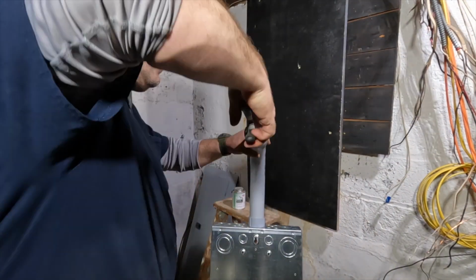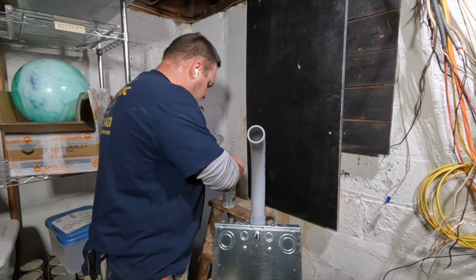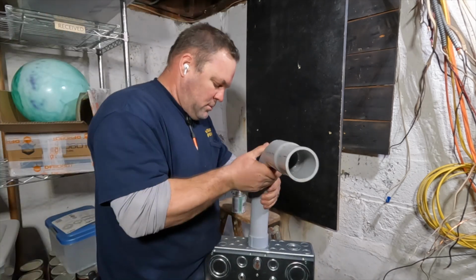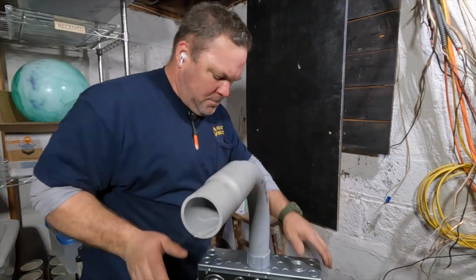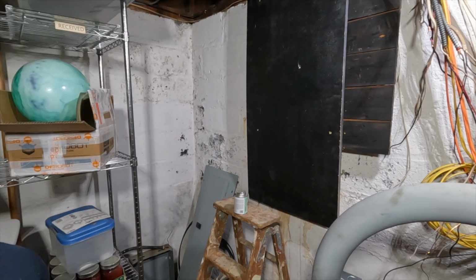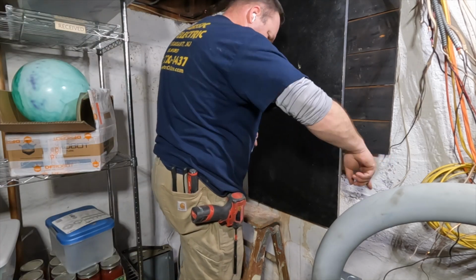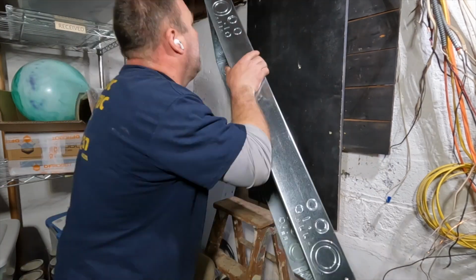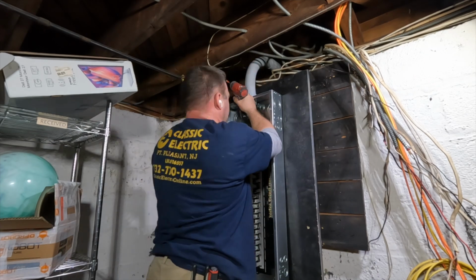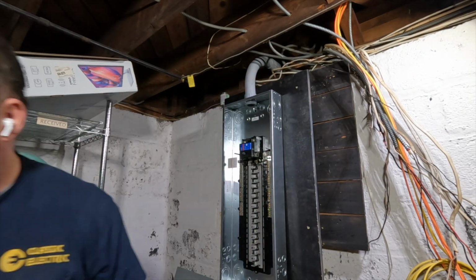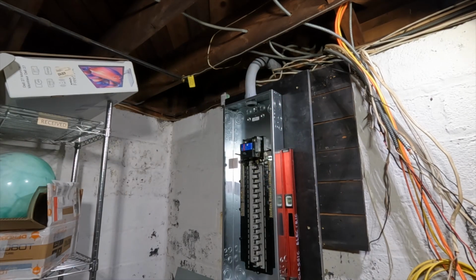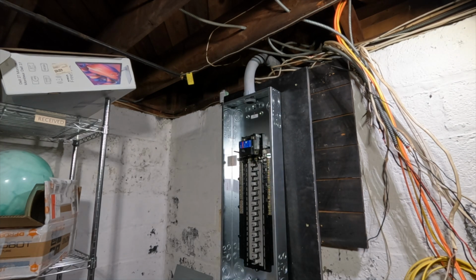Here I'm mounting the panel. As you can see, I already did a pilot hole, and now I've got my PVC, which I'm mounting to the board. That end of the 90-degree sweep goes into the back of the LB on the outside, so the service entrance conductors come through the PVC and the sweep into the top.